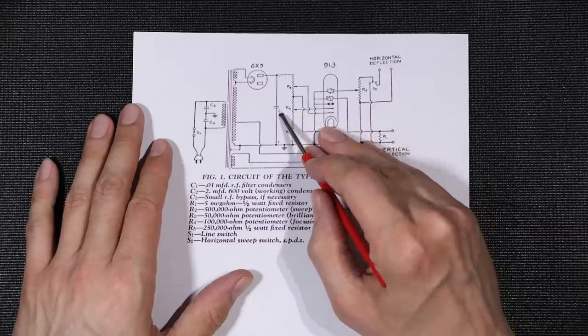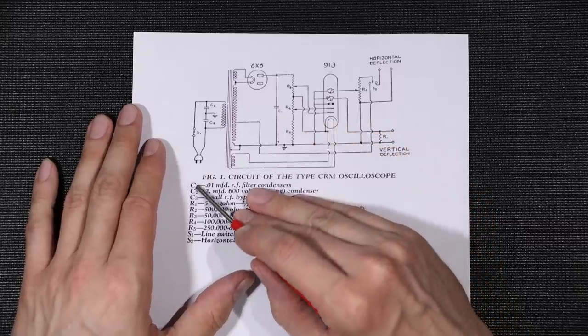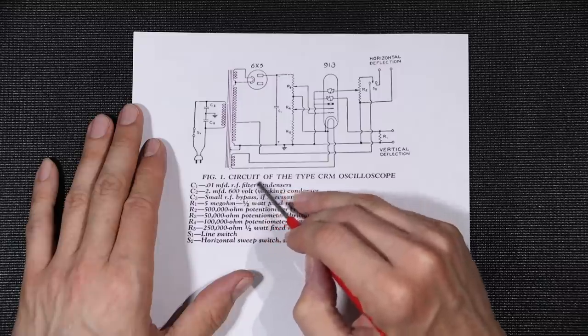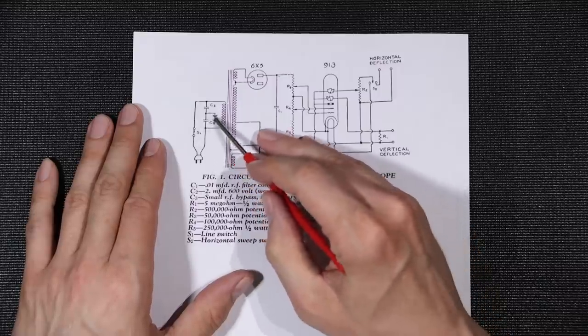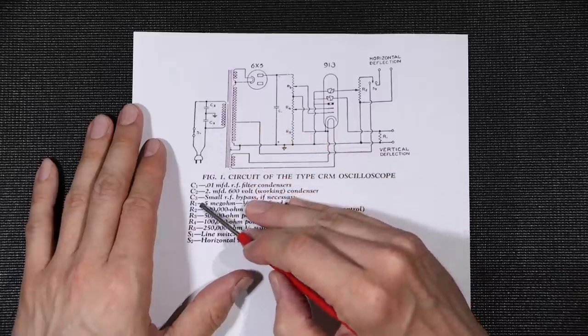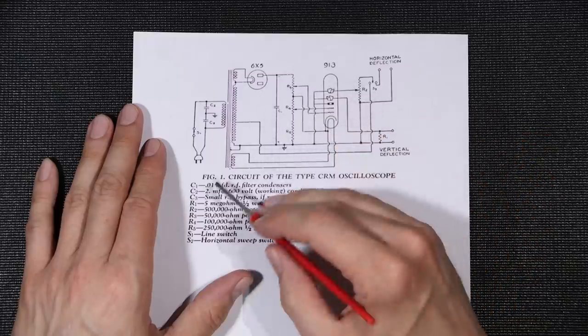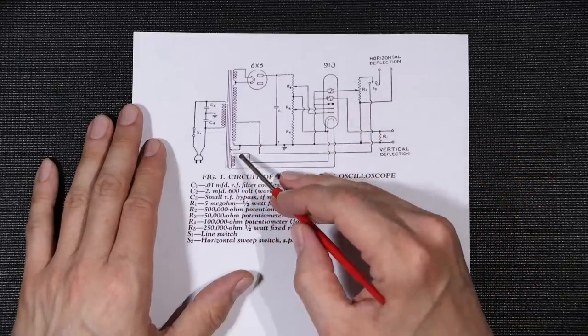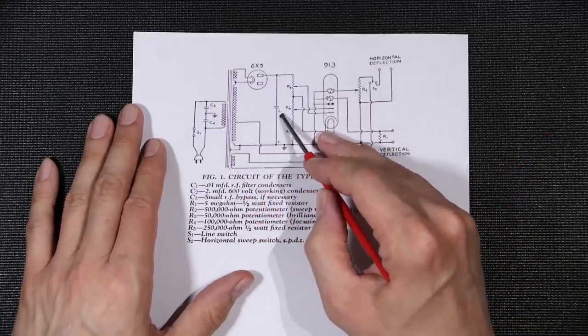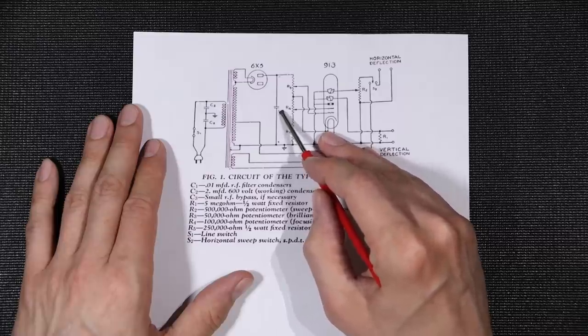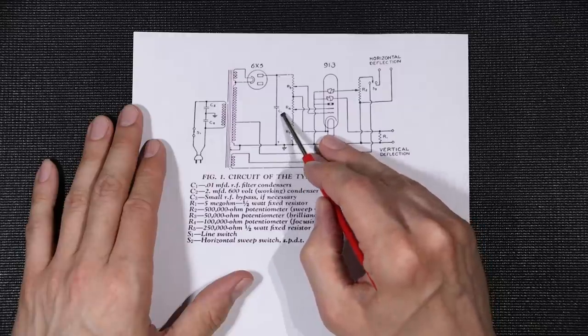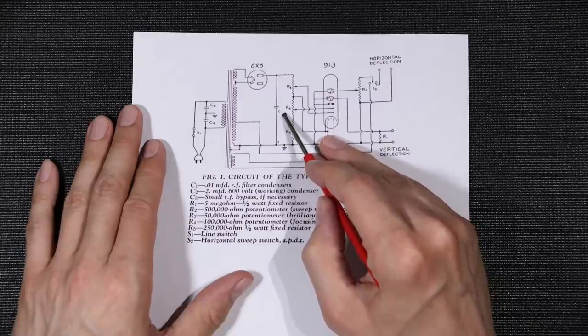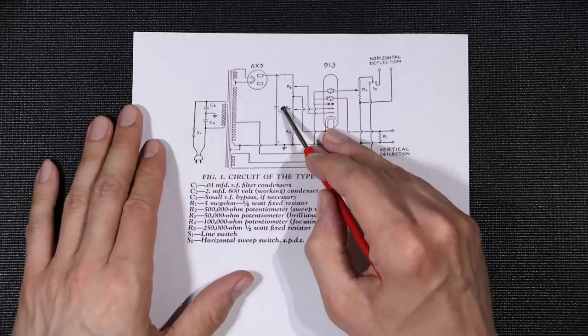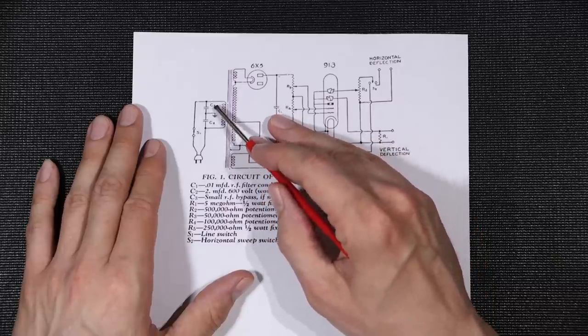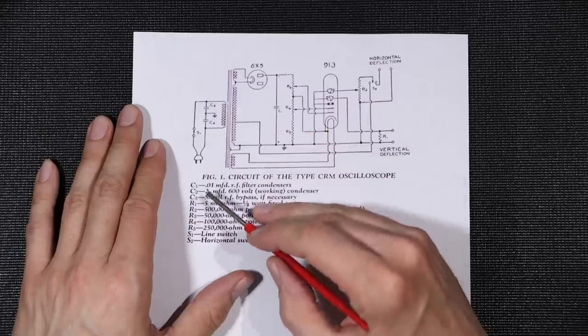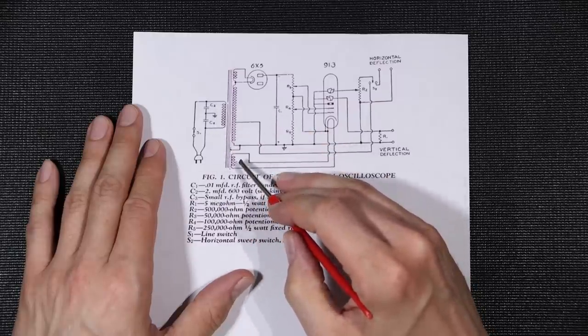Now you'll see that it looks like this says C1 here, and it says C1 0.01 microfarad RF filter condensers. Then it looks like this is C2, but yet we have a C3 and there is no C3 on this, so one of these might be C2 and C3. This is actually going to be C2, the 2 microfarad capacitor here on this side — this is not C1 like it looks on the schematic. So this is the 2 microfarad 600 volt cap here, and these could both be classified as C1 or C3. It's a small RF bypass if necessary.